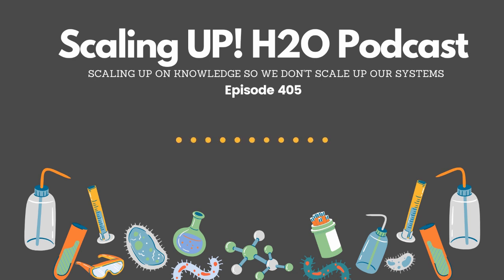What were some of the things you were measuring to make sure efficiency didn't drop off? Water chemistry analysis - understanding all the variation in the makeup water: pH, conductivity, all the components, ammonia, alkalinity, all that kind of stuff, and trying to address that type of fluctuation.